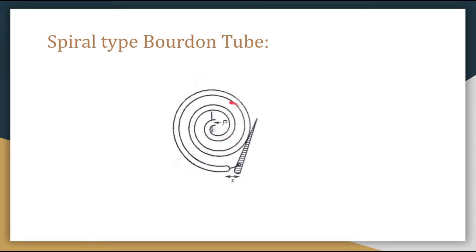In the spiral type Bourdon tube, the tubes are made by winding several turns with a flattened cross-section in the form of a spiral, as clearly shown in the diagram. When the pressure to be measured is applied to the spiral, it tends to uncoil, producing a relatively long movement of the tip. When pressure is applied and the spiral uncoils, the displacement of the tip will be much larger than in the C-type Bourdon tube.